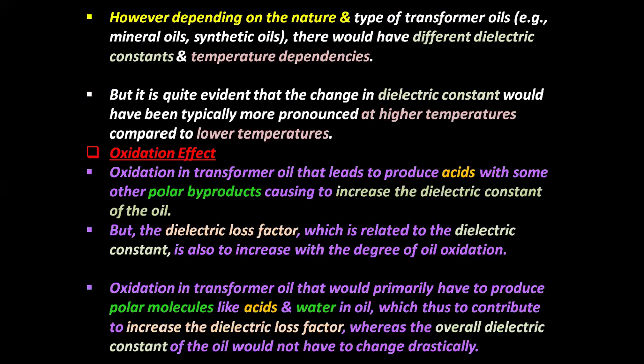compared to lower temperatures. Oxidation effect: oxidation in transformer oil leads to the production of acids with some other polar byproducts, causing an increase in the dielectric constant of the oil. But the dielectric loss factor, which is related to the dielectric constant, also tends to increase with the degree of oil oxidation.